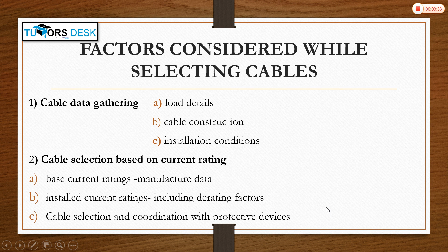The third is cable selection according to coordination with protective devices, meaning the protective devices we are using in the feeder or motor, which may be a fuse, a relay, or a circuit breaker. And the next is voltage drop. As you all know, whenever current flows through a cable, there is a voltage drop across it due to its resistance and reactance, which is given by Ohm's law. According to this equation, the voltage drop is directly proportional to the current and the impedance of the cable.